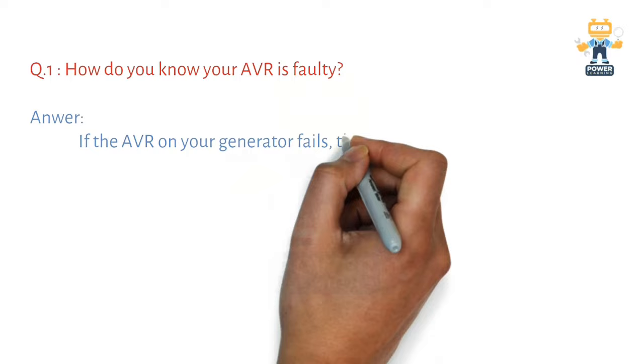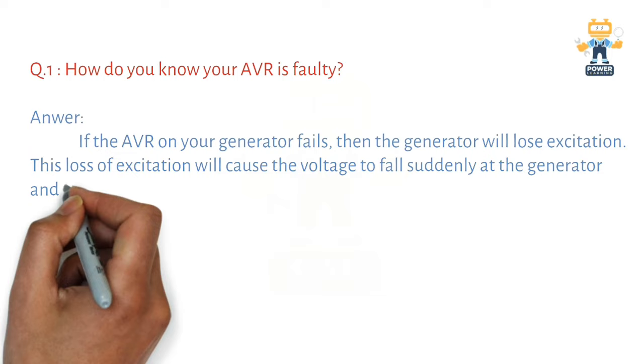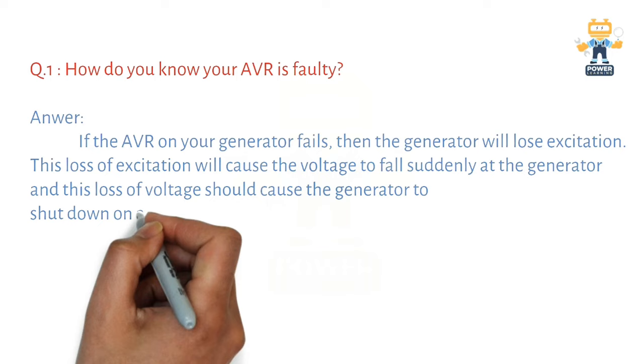How do you know your AVR is faulty? The answer is: if the AVR on your generator fails, the generator will lose excitation. This loss of excitation will cause the voltage to fall suddenly at the generator.